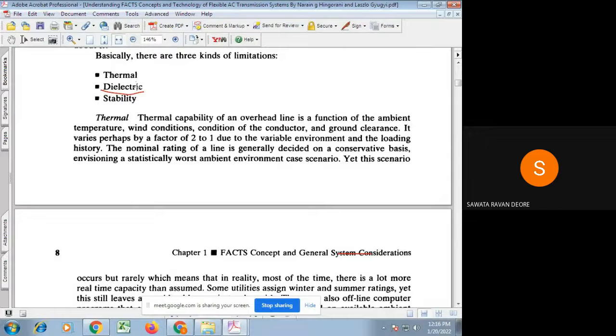Obviously, whatever voltage variation we are talking about, that is not under steady state condition. It means if any sort of transient takes place, let's say some fault happens or a sudden drop in load takes place, then under those circumstances, whatever rise in voltage takes place should be such that it does not puncture the dielectric material between the conductors or between the ground clearance. The spark should not take place under that transient condition. So by taking care of all this, accordingly the transmission lines are loaded.